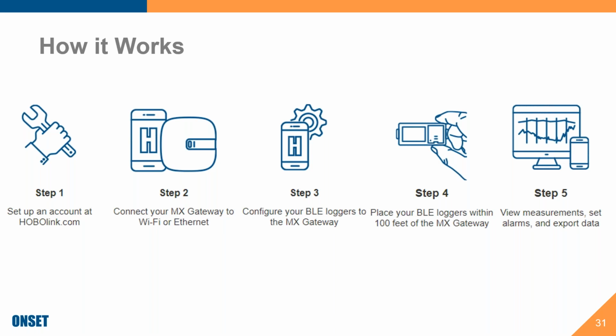Initially, when you set this up, you're going to want to create a HOBO Link account. You use your mobile device to initially connect to the gateway to set up the Wi-Fi and Ethernet settings. The gateway is going to be given the username and password, so it goes up to the appropriate HOBO Link account. Next, you're going to configure your loggers using your mobile device as well. You'll set the recording interval, give it a name, set any alarm thresholds, and that too will have the HOBO Link username and password, so that goes up into the appropriate cloud.